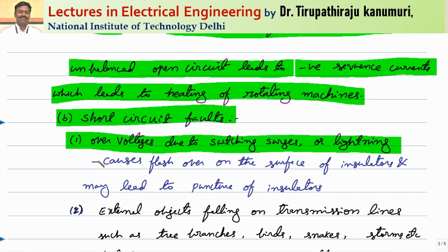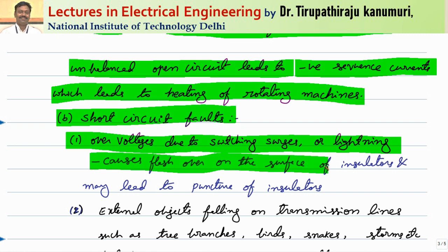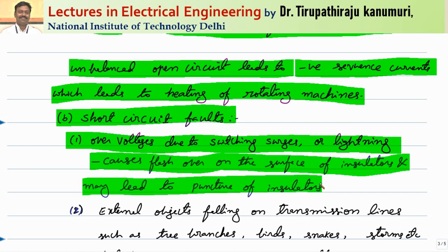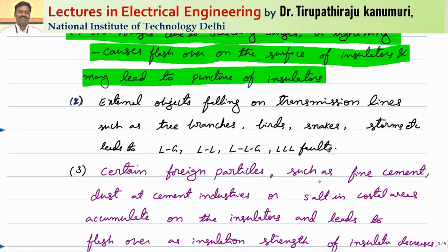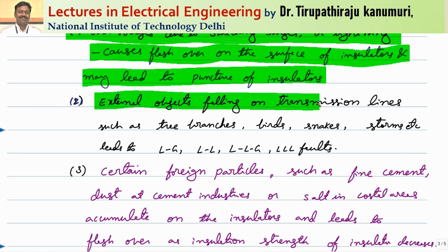During switching transients, very high voltages arise, causing flashover on the surface of insulators in the case of overhead lines, or complete dielectric breakdown in the case of cables or machines. This may lead to puncture of the insulators or breakdown of insulation in cables. The second possible reason is external objects falling on transmission lines — such as tree branches or birds — which can lead to short circuits.